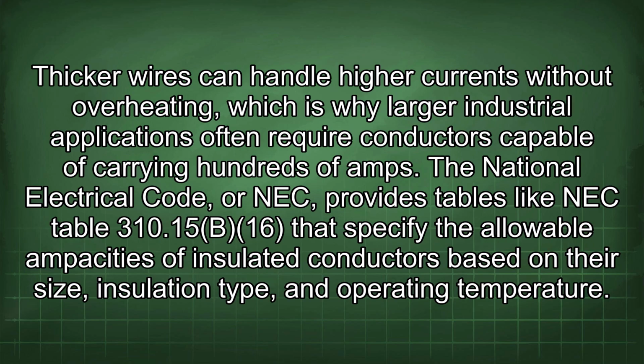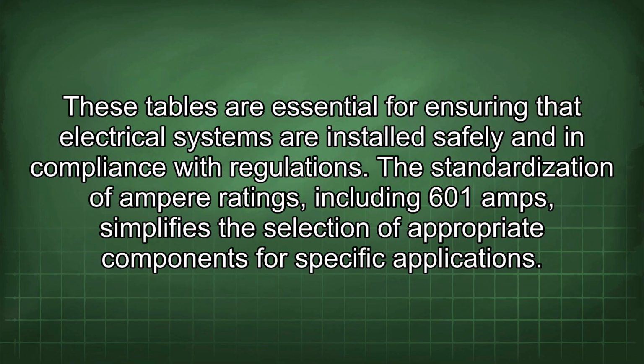The National Electrical Code, or NEC, provides tables like NEC Table 310.15(B)(16) that specify the allowable ampacities of insulated conductors based on their size, insulation type, and operating temperature. These tables are essential for ensuring that electrical systems are installed safely and in compliance with regulations.